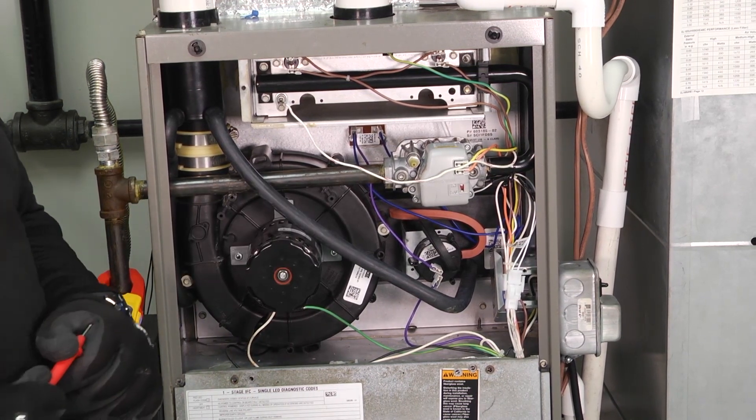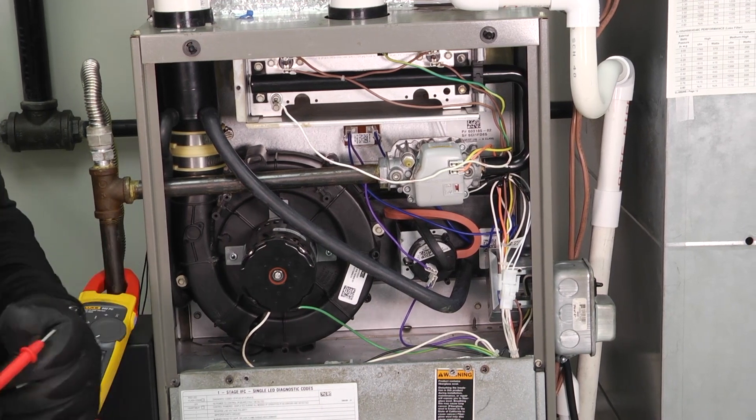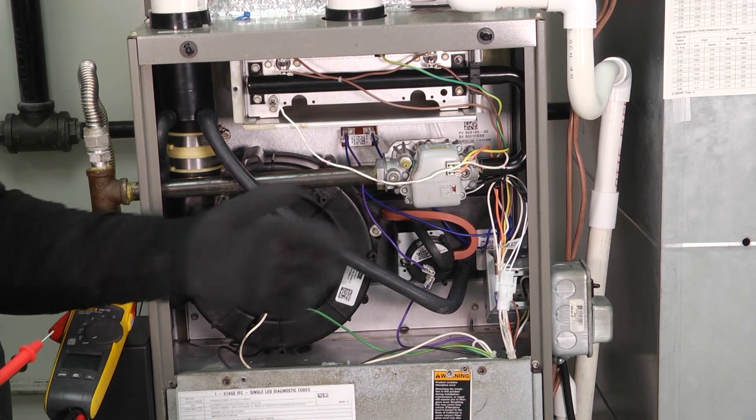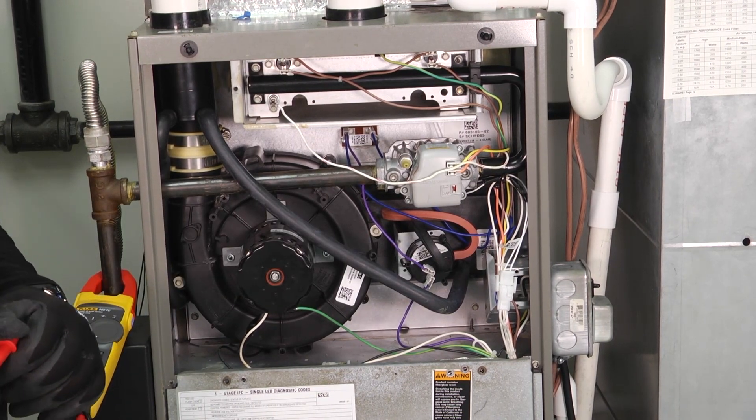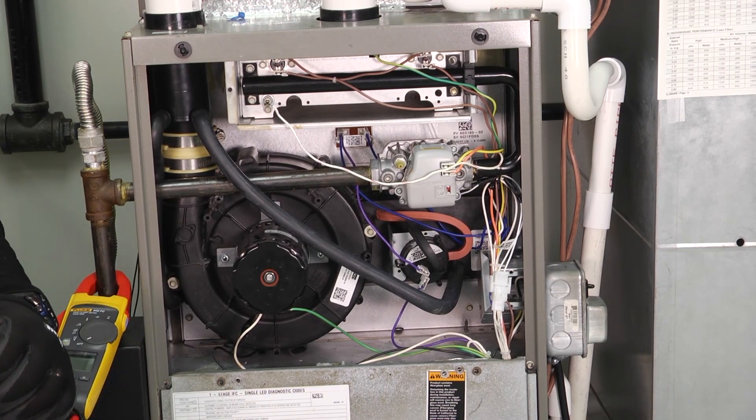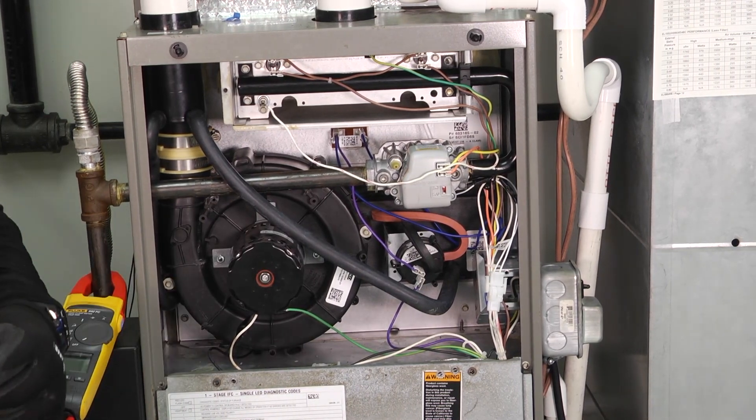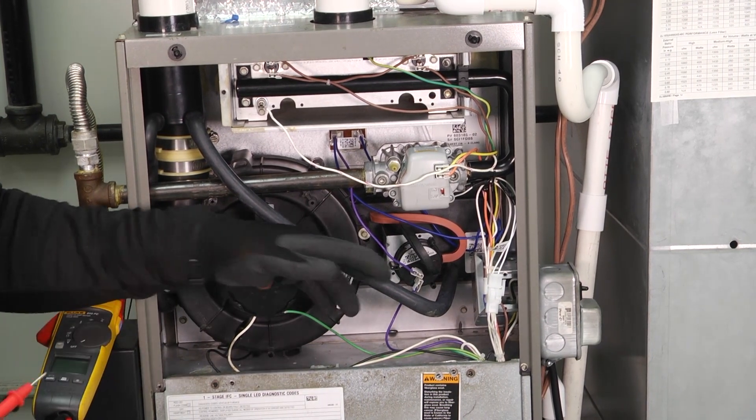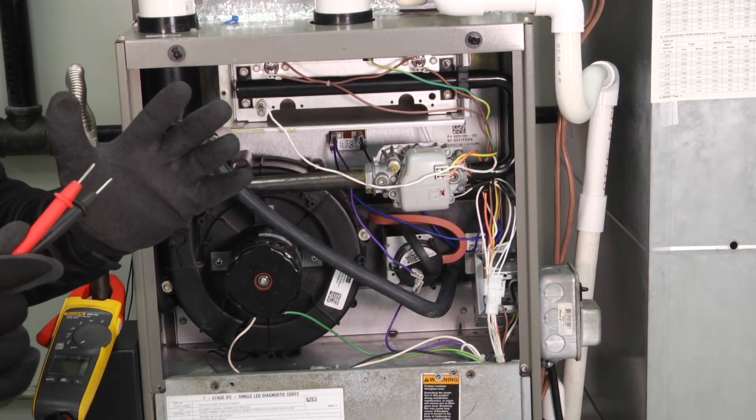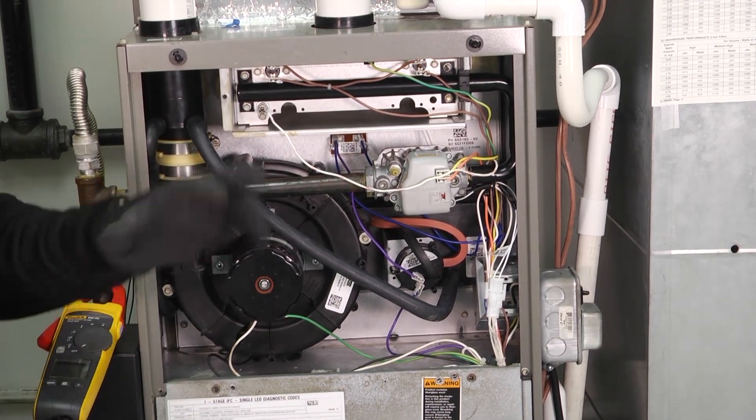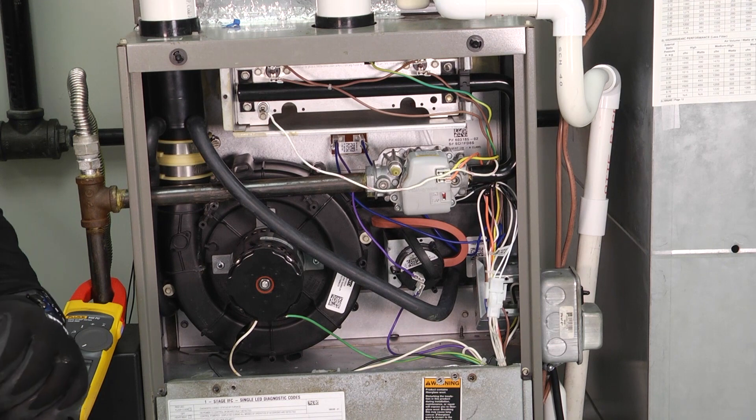One of the things that you have to keep in mind is that there are a couple different types. Silicon carbide and silicon nitride are the two different types that we have. And so be sure that you understand and you know which one you have in your system. Reason being is the resistance or the ohm tolerances from the manufacturer, which states that it's in a safe ohm range or not, are going to differ between the two.